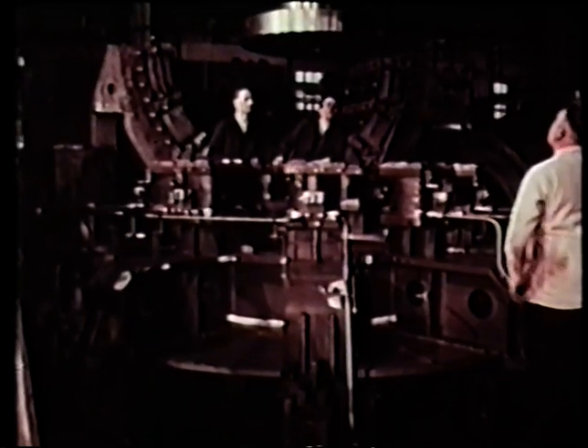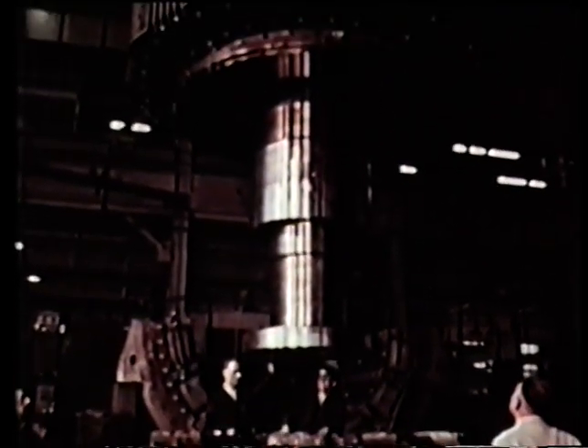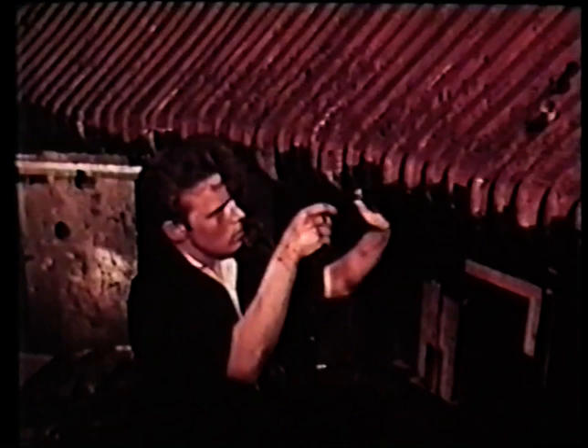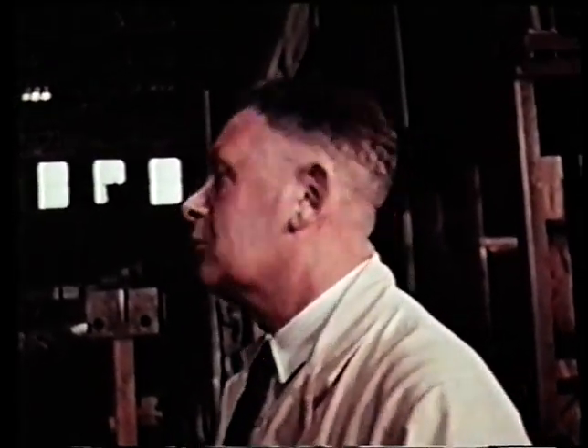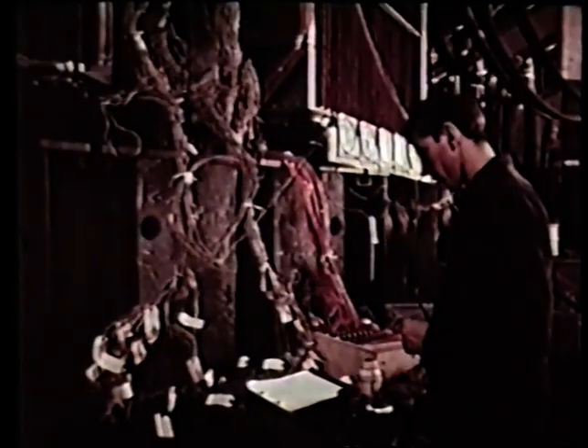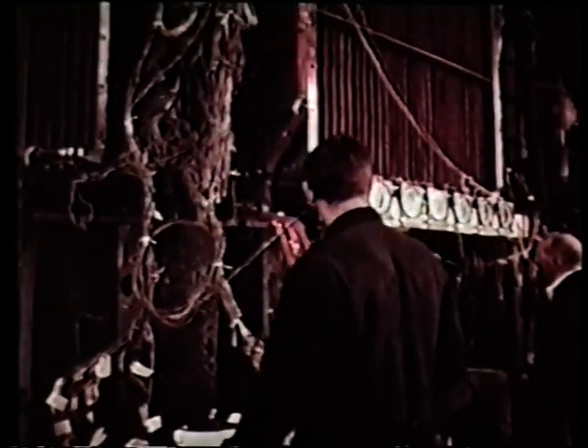On the motor generators for Cruachan, the figures of MVA per pole are among the highest in the world and represent a notable achievement for British industry. Braking is by friction pads, applied when the machine has run down to 20% speed. After full assembly, works tests included determination of losses, temperature changes, reactances, airflow, and noise level. The stator was split into three sections for transportation.